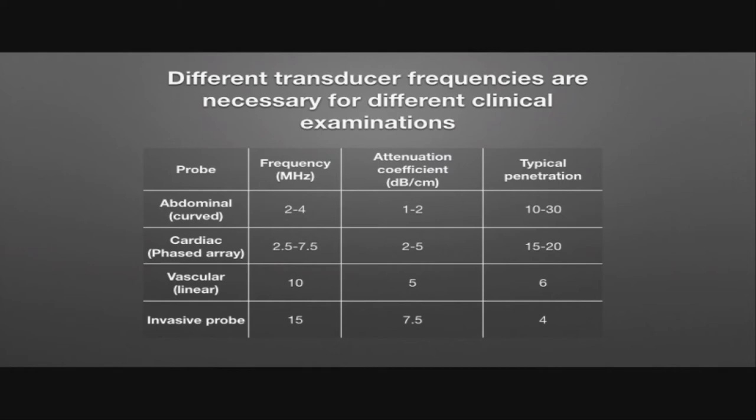Next up are the vascular probes, which are the linear probes, operating at around 10 MHz with a higher attenuation coefficient and typical penetration of 6 cm. Finally, the invasive probes, like the obs and gynae probes, operate at 15 MHz. They have an even higher attenuation coefficient and typical penetration of around 4 cm.